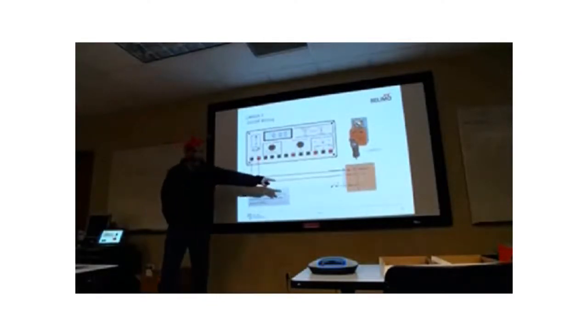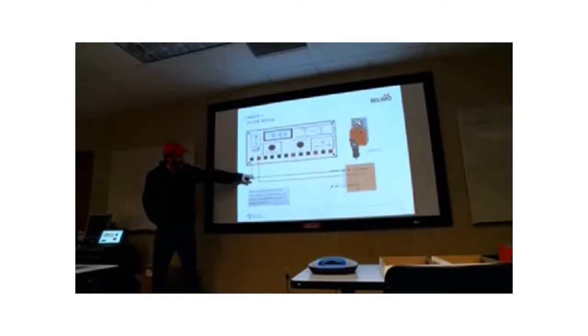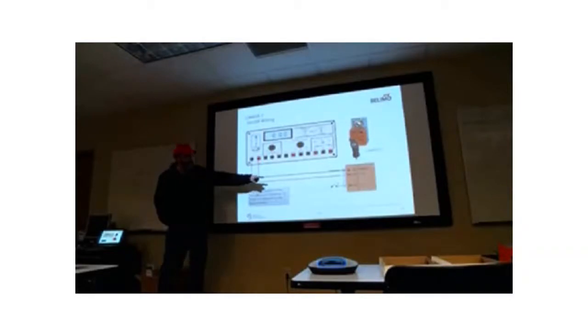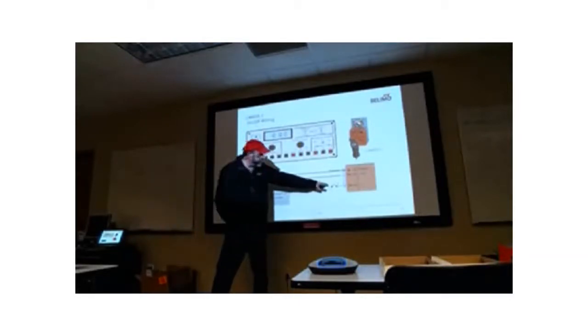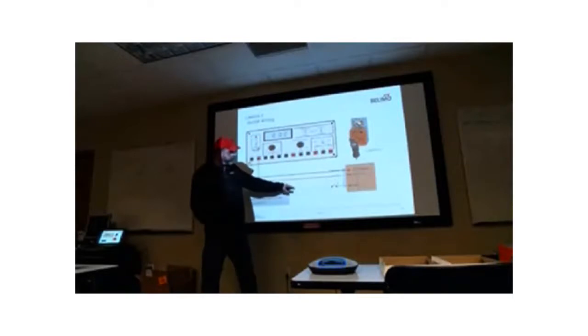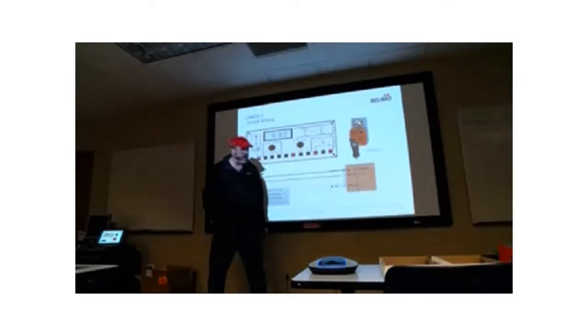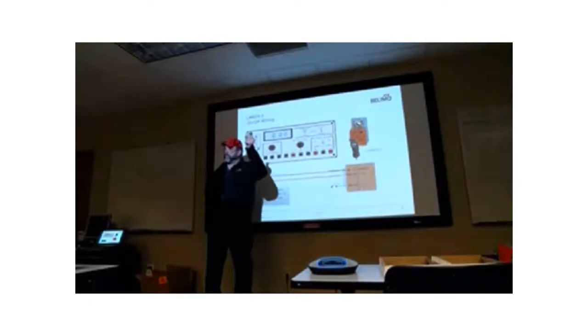Look up on the screen here. You got red, white is 1 and 2. You got number 3 wire, which is the white wire, which should typically go to terminal 3. What you're essentially doing is, when you short that red wire to the white wire, when that white wire hits there, it actually reverses the voltage applied to the bridge in the motor, and it reverses the rotation of the motor.